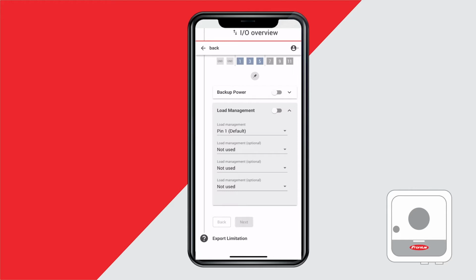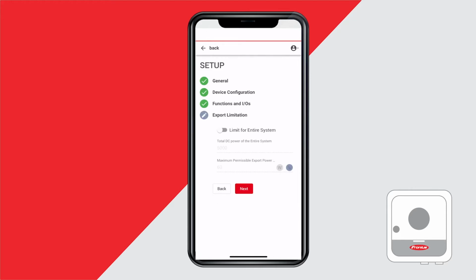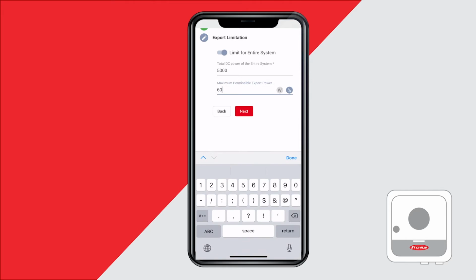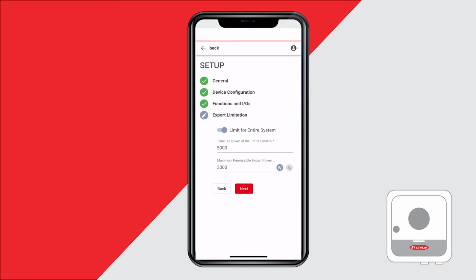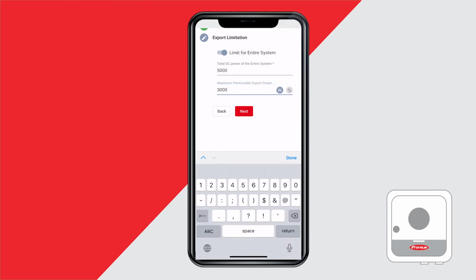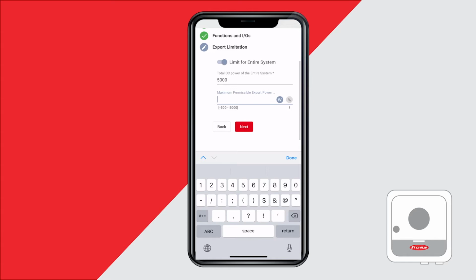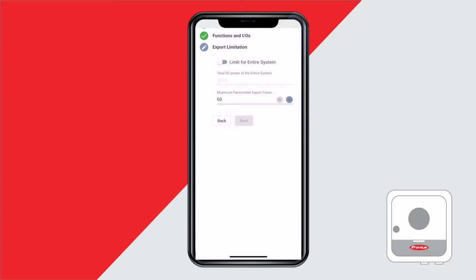Finally, you have export limitation, where you can limit the entire system if required. You enter the total DC power of the system, for example 5000 watts, and the maximum permissible export power. Here it's selected in percentage, but you need to select watt instead — I'd always recommend using watts, it's easier. Then you just put your export limit value. We're not using it here, so I'll turn it off and press next.